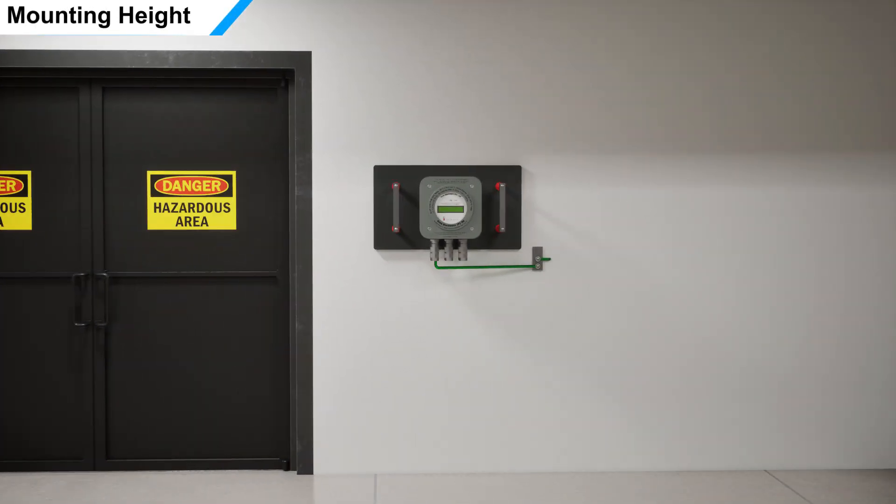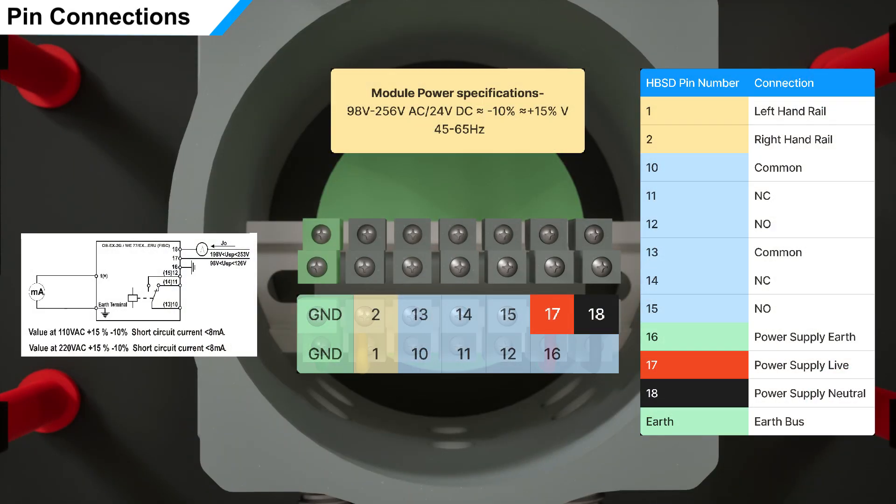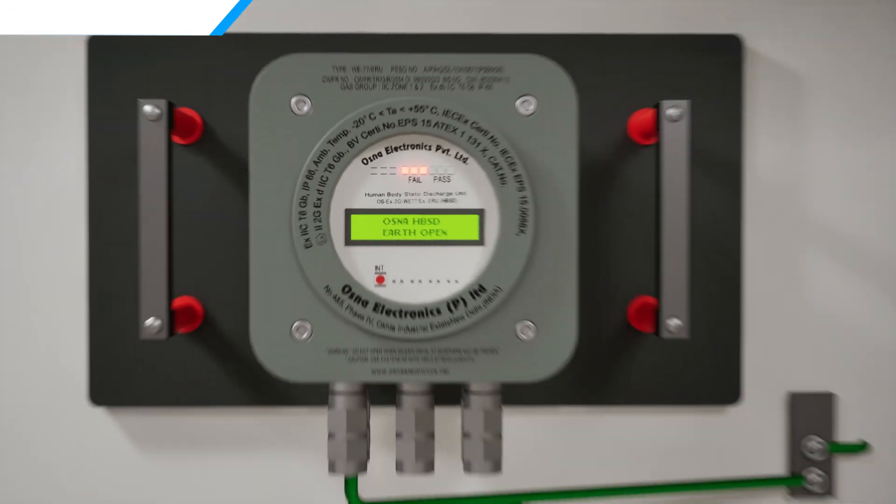Position the HBSD at shoulder level height to ensure optimal visibility and accessibility. Connect the device to a power source within the range of 98V to 256V AC or 24V DC, ensuring that the voltage falls within the specified tolerances of -10% to +15% and the frequency is between 45 to 65 Hz.